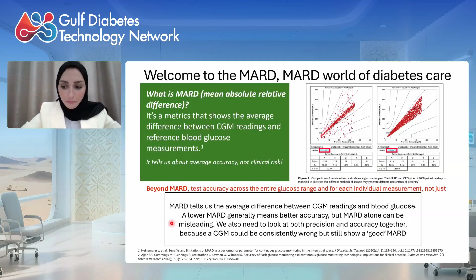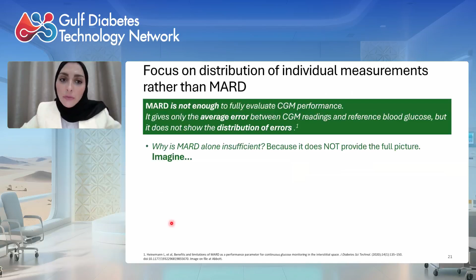So does the MARD give us the full picture and evaluate the full performance of a CGM? In fact, no. The MARD doesn't evaluate the distribution of error. Imagine someone wanted to cross a river, he is 2 meters tall, and he was told that the average depth of the river is 1.5. Yes, if we measure near the shore, the depth is 1, and in the center the depth is 2.5, this gives an average of 1.5. And if he crosses the river, he will drown in the middle. Why is that? Because they gave him the average of the river by taking the edge and the middle. So exactly, MARD is like knowing only the average depth of the river. It does not tell us about the deep spots that could be dangerous.